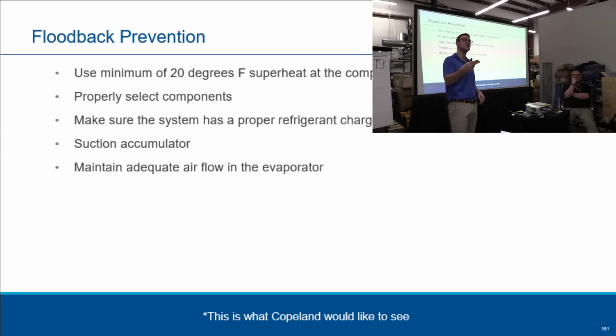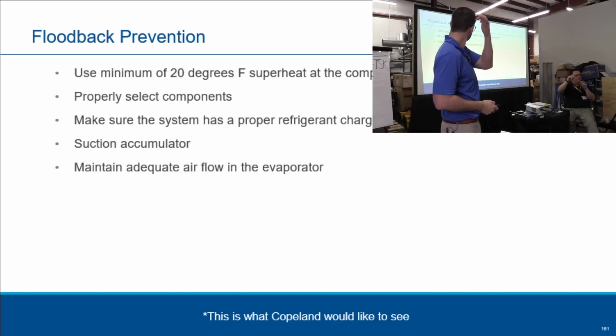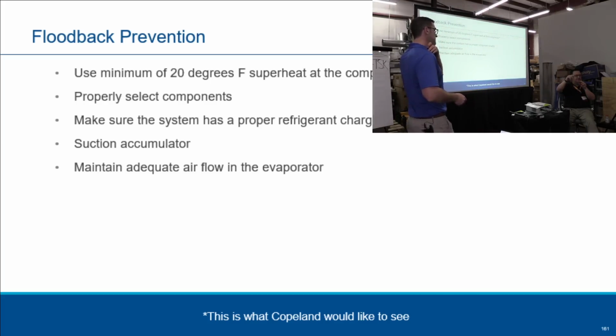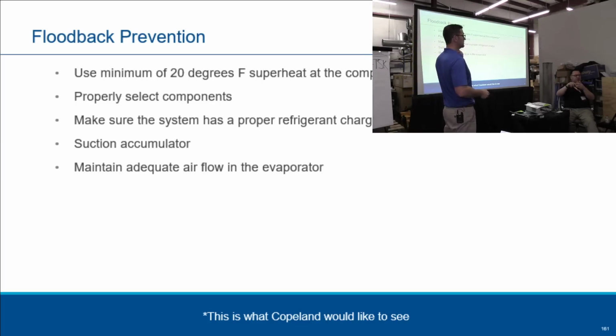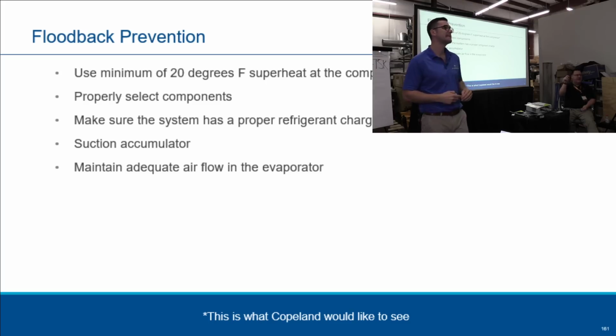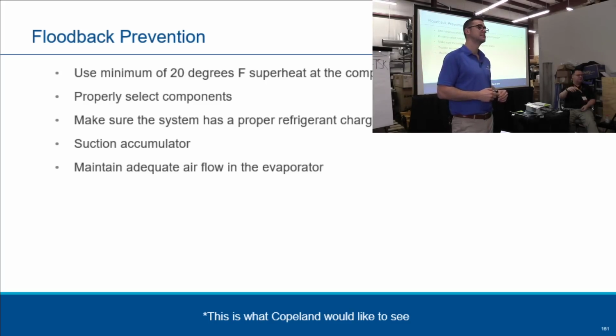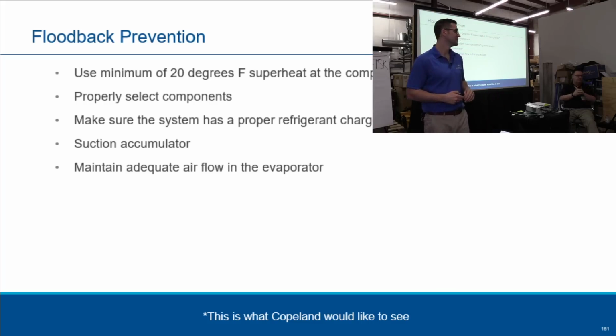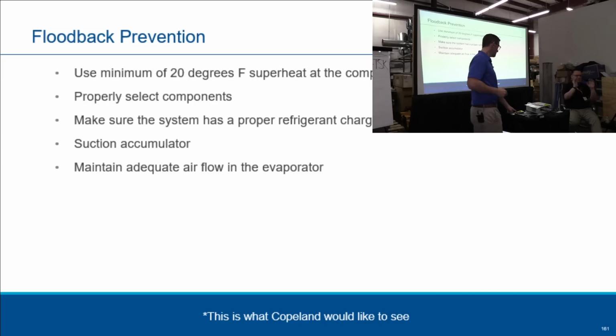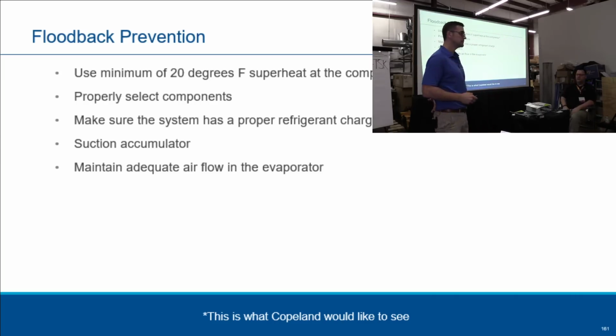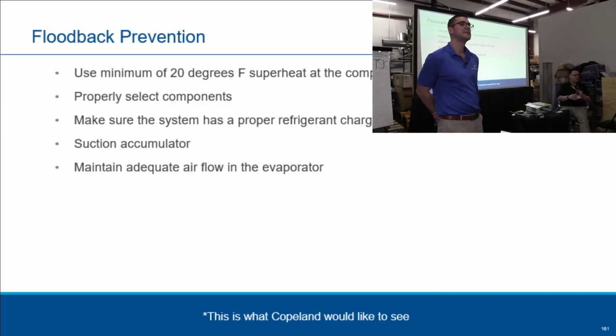And then there are some additional cooling requirements for those compressors. Just as Trevor showed you earlier, there's a new feature on that Copeland Mobile. If you go back in that diagnostic part and hit it, it will tell you the superheat and what the return gas is and what it should be, okay? So just so you know, play with that Copeland Mobile. We're all self-taught and it's easy to go around through that. Just start pushing things and you'll figure it out. It's pretty easy. Dave. Also, you want to look at the discharge line temperature and be below 225.